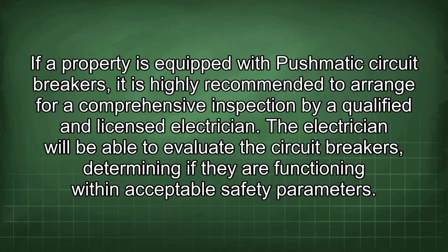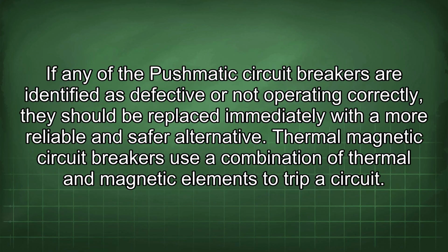If a property is equipped with Pushmatic circuit breakers, it is highly recommended to arrange for a comprehensive inspection by a qualified and licensed electrician. The electrician will be able to evaluate the circuit breakers, determining if they are functioning within acceptable safety parameters. If any of the Pushmatic circuit breakers are identified as defective or not operating correctly, they should be replaced immediately with a more reliable and safer alternative.